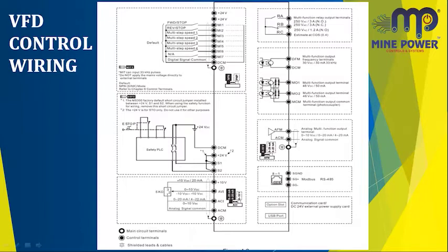And last you see SGND, SG plus, Modbus, SG. It is a communication port between the PLC and the drive, an RS485 communication port. From the program fed in the PLC, the data is sent to the drive through this port and the motor speed can be controlled. There are also other options: slots for communication cards, and USB ports, which you can use for this purpose.